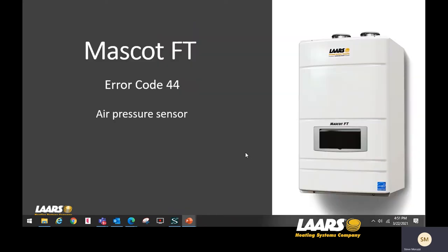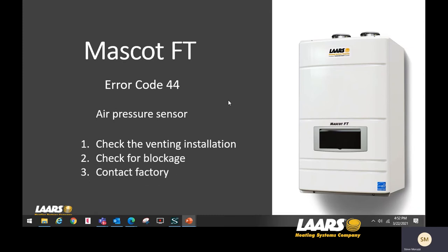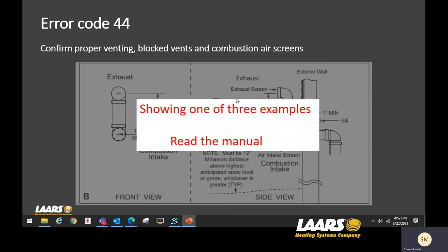Next, error code 44 — the air pressure sensor. Again, check your venting installation first. Most manufacturers, including us, see a lot of venting installation problems that can cause the 44 error code. Also check for blockage. If everything checks out, contact the factory.